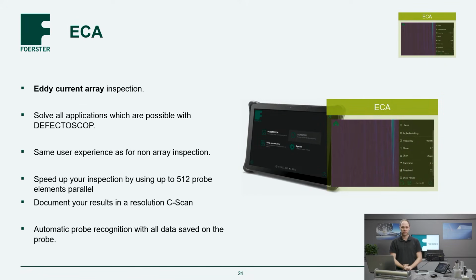Now we directly move to eddy current array testing. The eddy current array inspection solves in the end all applications which are also possible with a single probe, but with a higher number of probes. So if you make a scan, as an example, with a 1.5mm probe and scan line by line, with an array you can use up to 512 probe elements in parallel and do one scan, and it's much faster and safer to test with such an array probe. The array software will have the same user experience as for non-array inspection, so there is no additional training necessary to do eddy current array testing. If you are able to do standard eddy current testing, you are also able to do array testing.